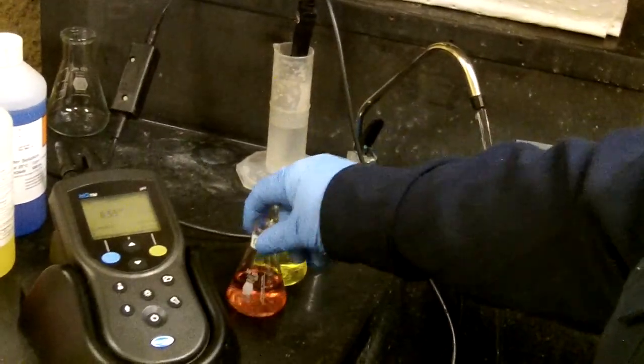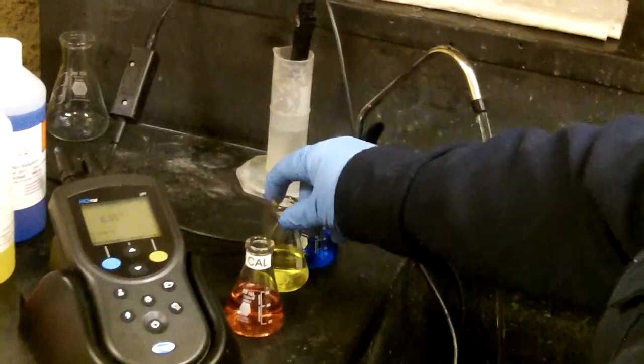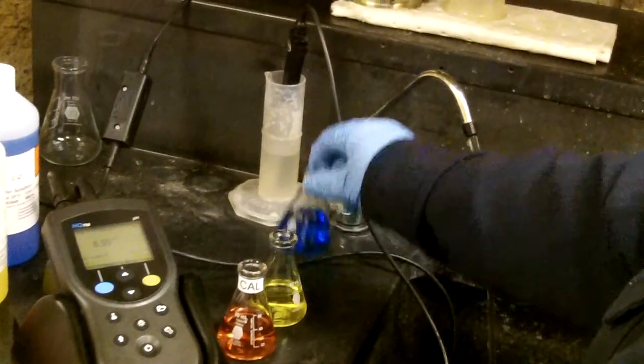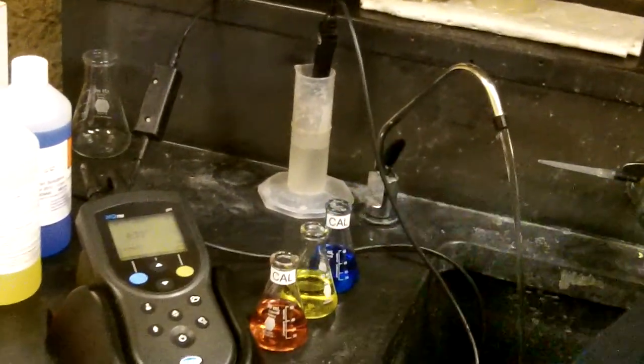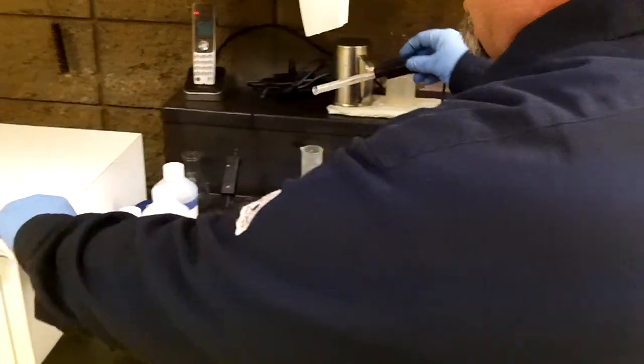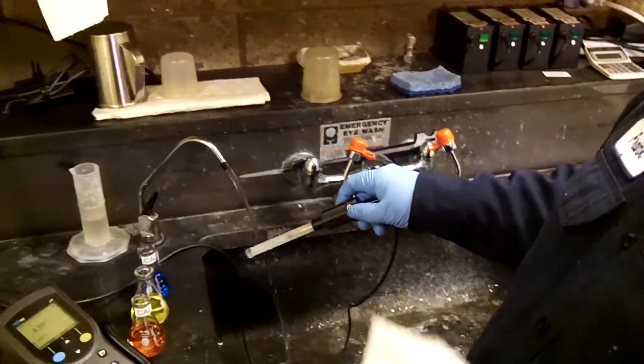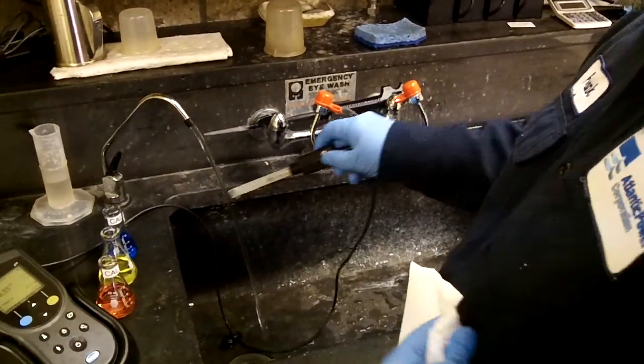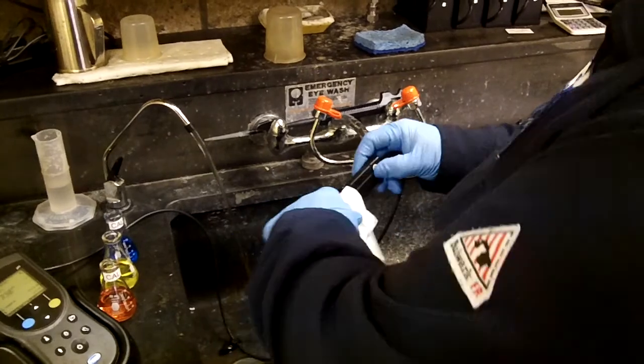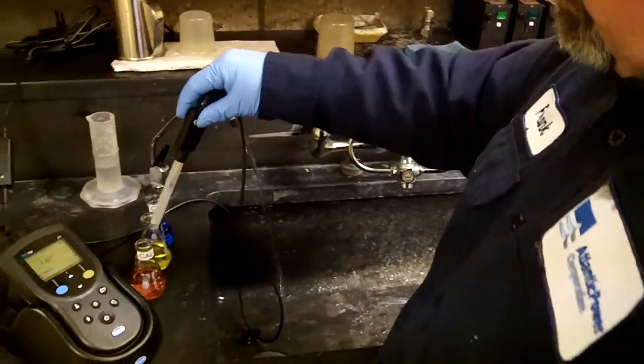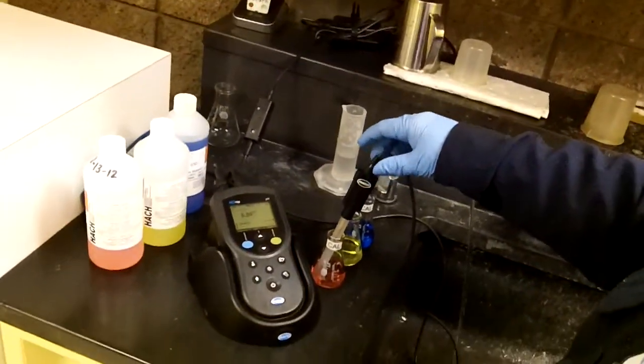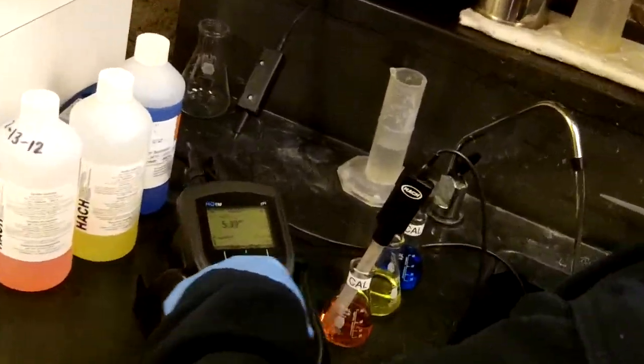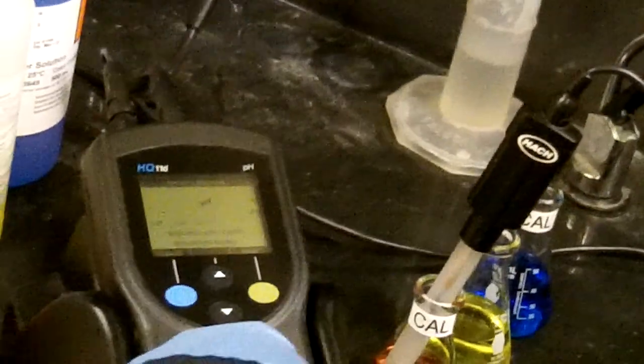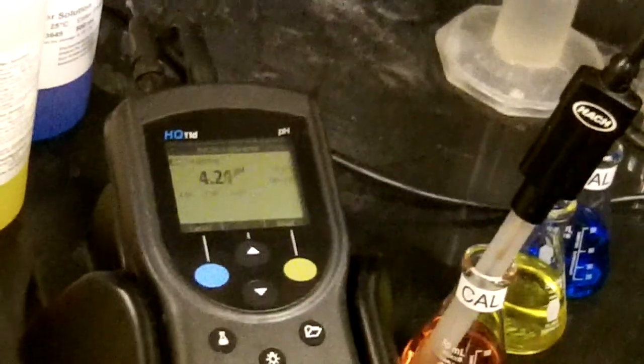I just right now put fresh buffer solution in each one of these. So these are all brand new buffer solutions, okay? So we're going to take our pH sensor probe that we have in our storage solution. We're going to rinse it with DI. We're going to wipe it dry. We're going to put it in the 4. Start with 4 always. And hit calibration. And then hit read, okay?